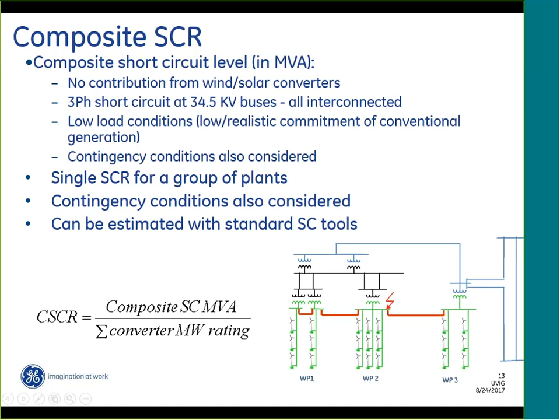So generally speaking, as you can probably see from this very simple description, the mechanics to calculate a short circuit ratio are relatively simple. You can use a short circuit tool, and you obtain these numbers, and you're actually describing phenomena that's quite complex. So it's a very simple index that describes complex phenomena. So there are limitations to this.